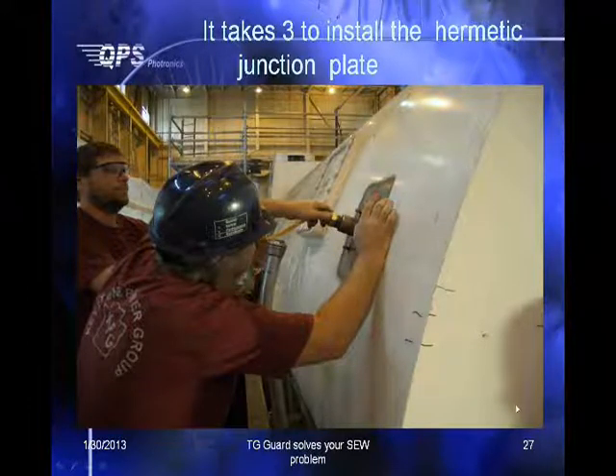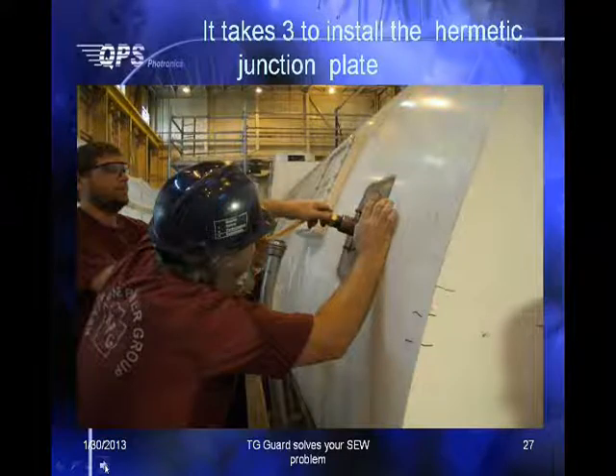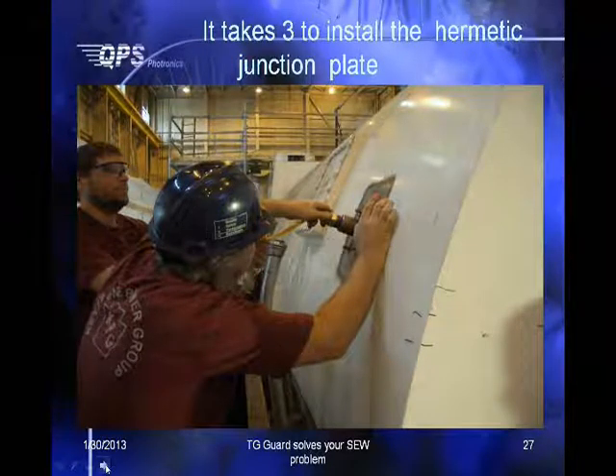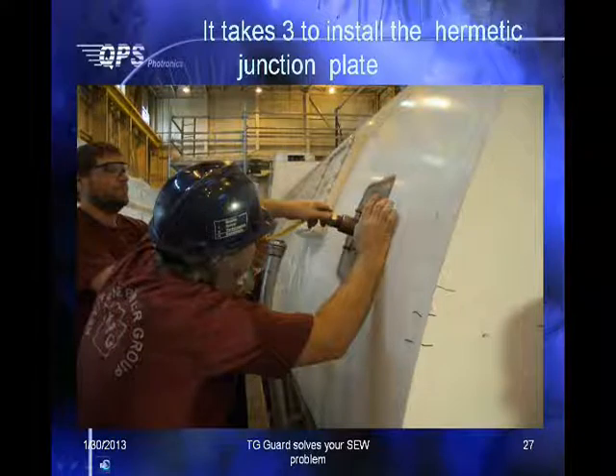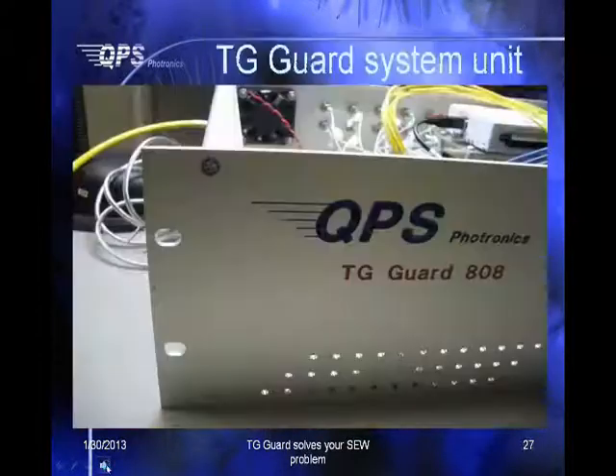Our field engineer works inside the generator, following the motion so we don't twist the fiber. This is another sensitive feature of our technology: it's not electrical. With electrical wire, you don't mind twisting, turning, or folding it into a right angle, but you can't do that here. Remember, fiberglass is still glass, and the way it guides light requires a minimum curvature of 30 millimeters, so you can't make very sharp turns.